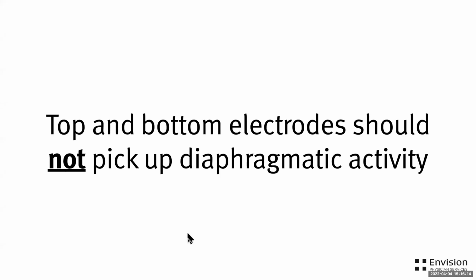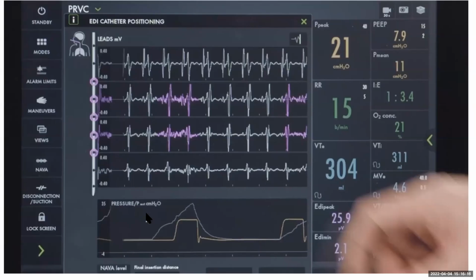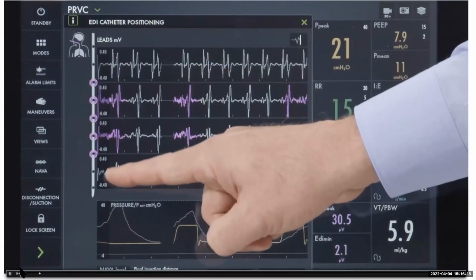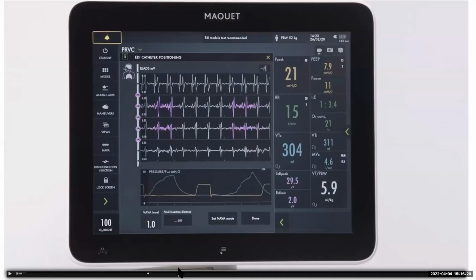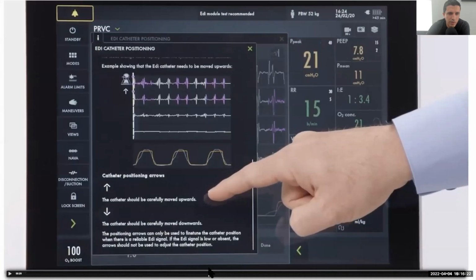Sorry to interrupt, but does that mean that you don't need to confirm position with imaging? That's correct. Oh, wow. So this is an example of how the EDI catheter is too high up, right? So you see 3 electrodes at the top are firing, and all the other electrodes are probably in the stomach. So you're probably missing some of the diaphragm, and you want to make sure, like what we were talking about, that you have some electrodes above and below that are not activated.